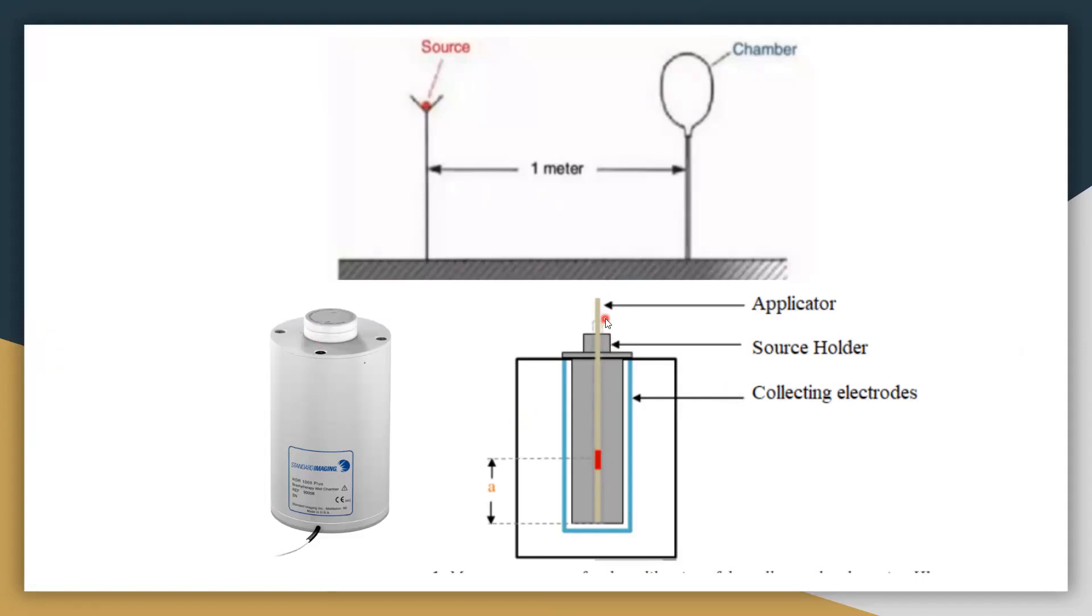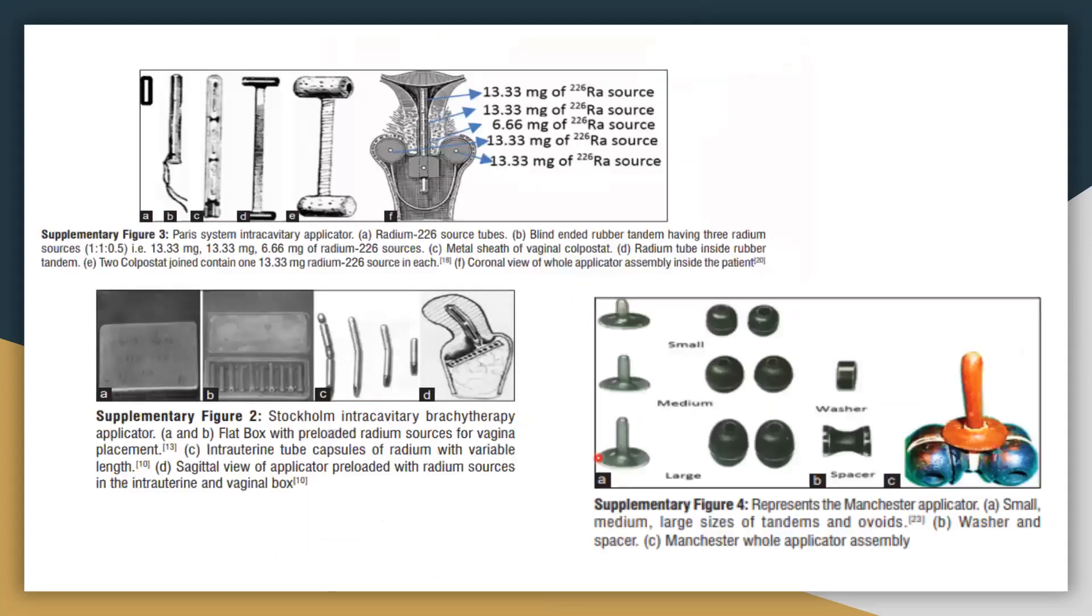So in practice, re-entrant well chamber was used, which has an applicator source holder and the electrodes. The source gives the higher dose at certain position, charge collected, and then air kerma strength was measured. These chambers are calibrated from PSDL, primary standards dosimetry labs. That's a classical model, radium sources replaced, and the typical source stays in a different position for the typical pear-shaped isodose lines.